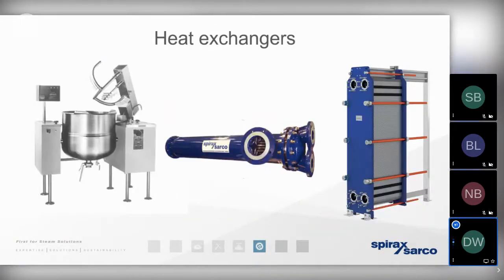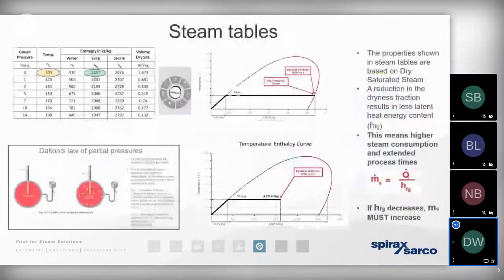So an example of a closed loop system could be a jacketed vessel, a shell and tube heat exchanger, or a plate heat exchanger. But the important thing to bear in mind is that it's important that we keep that steam as dry as we possibly can. So I just want to come back to the steam table slides that we looked at earlier.